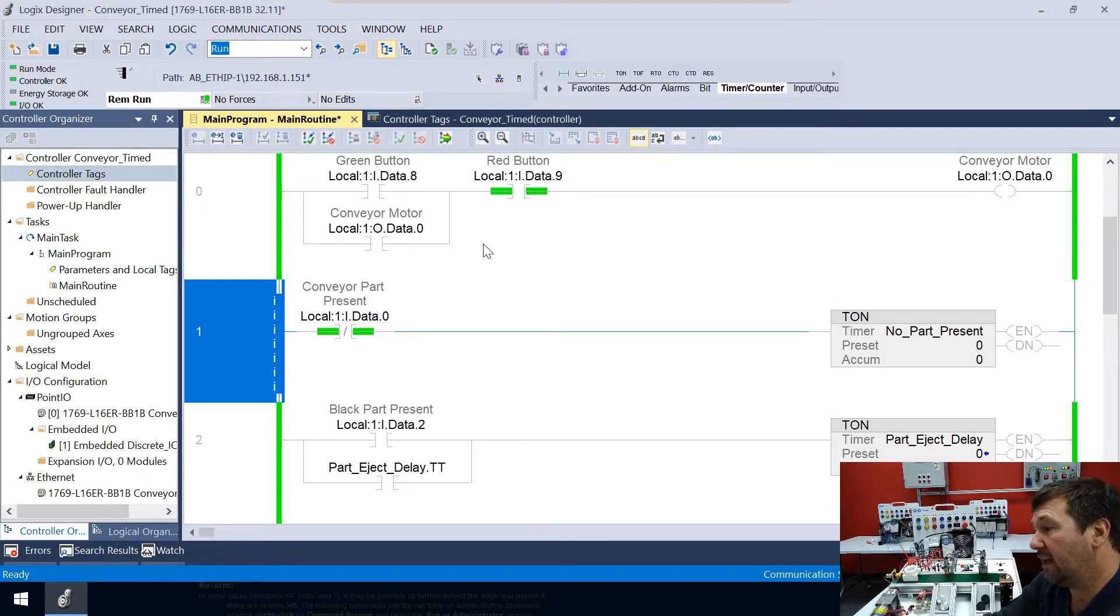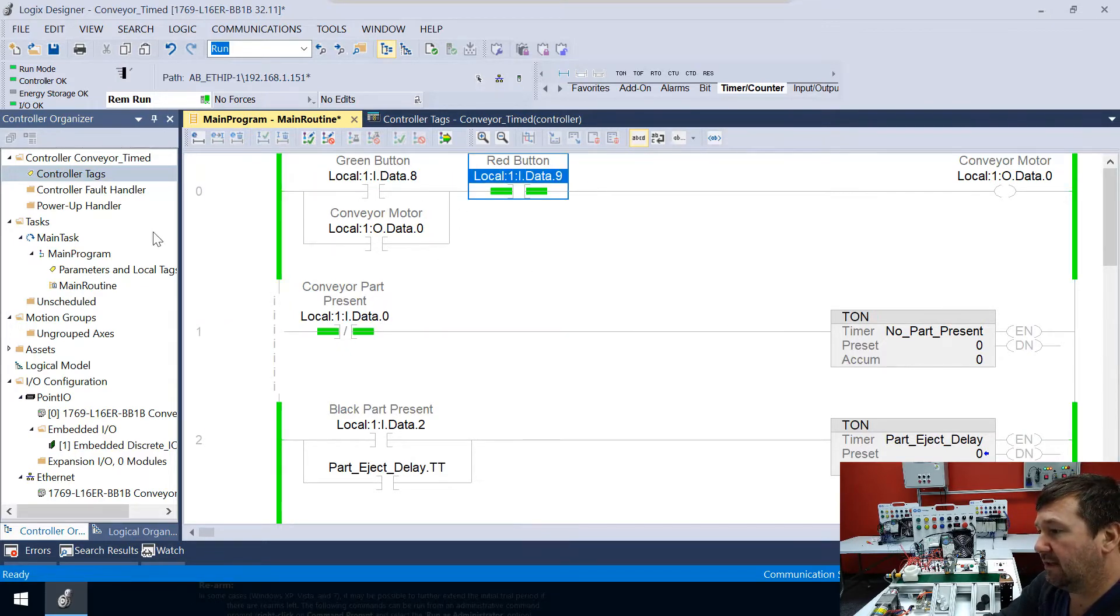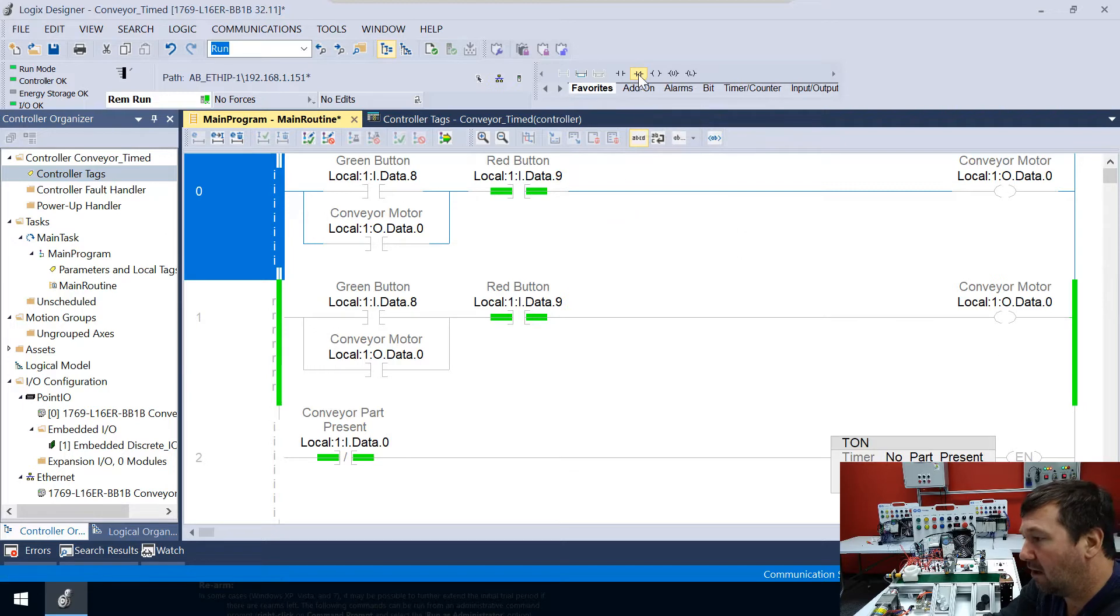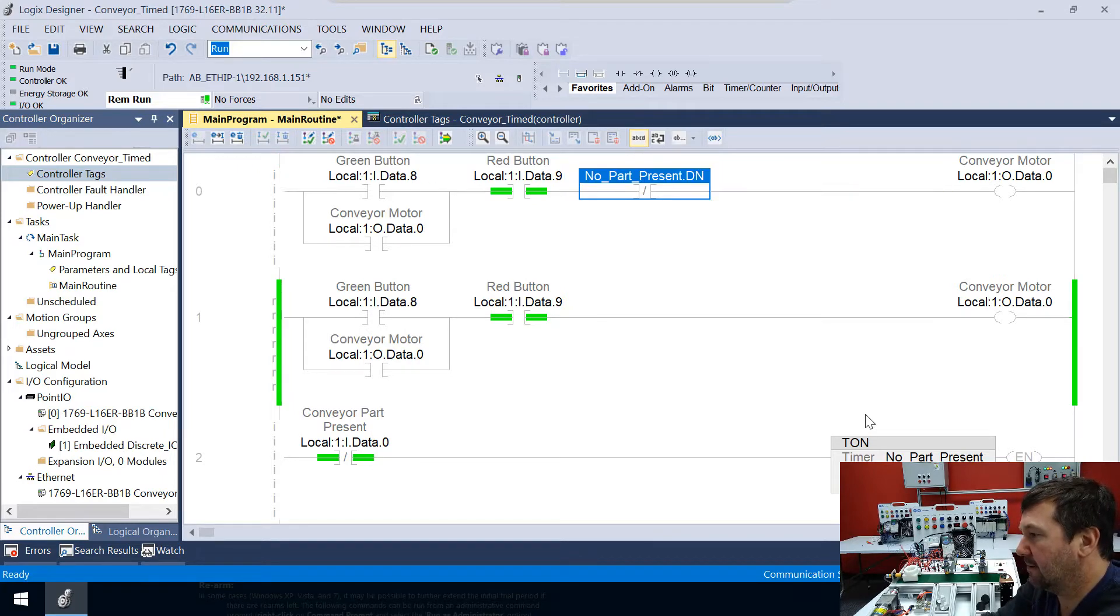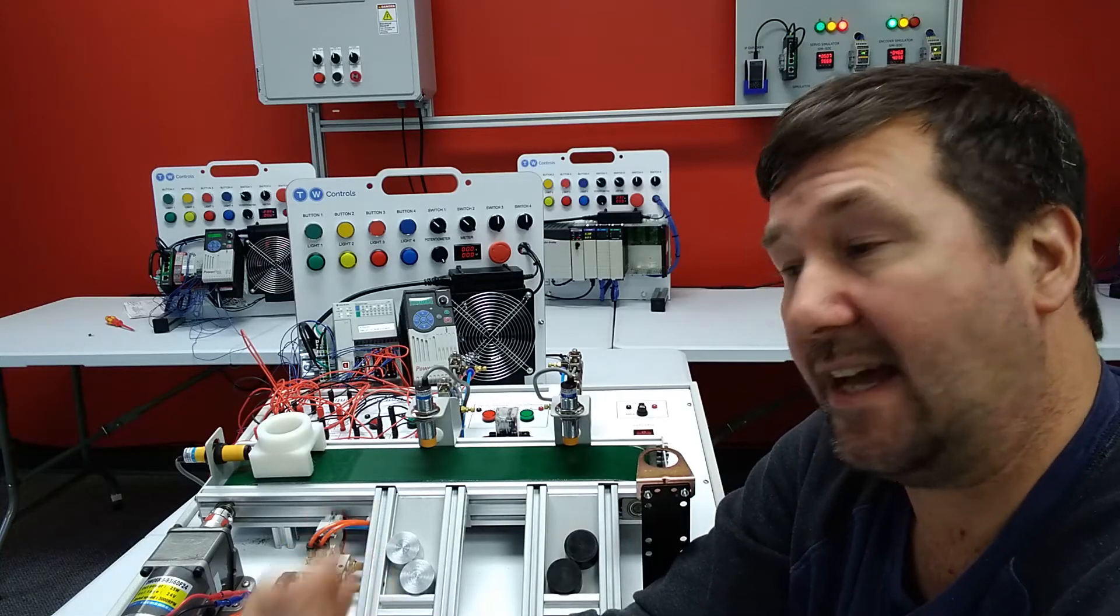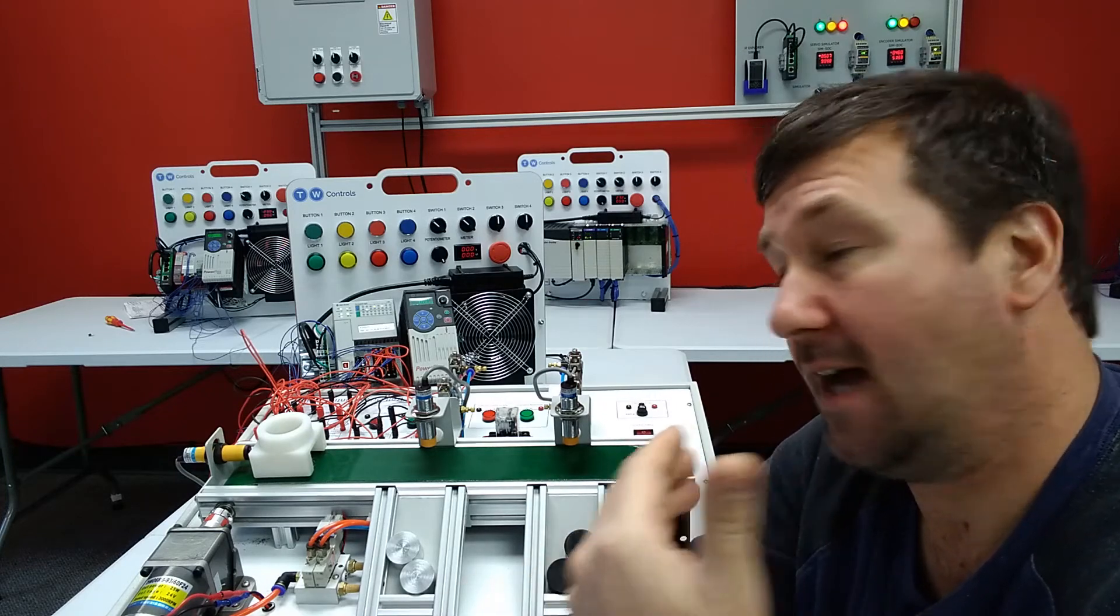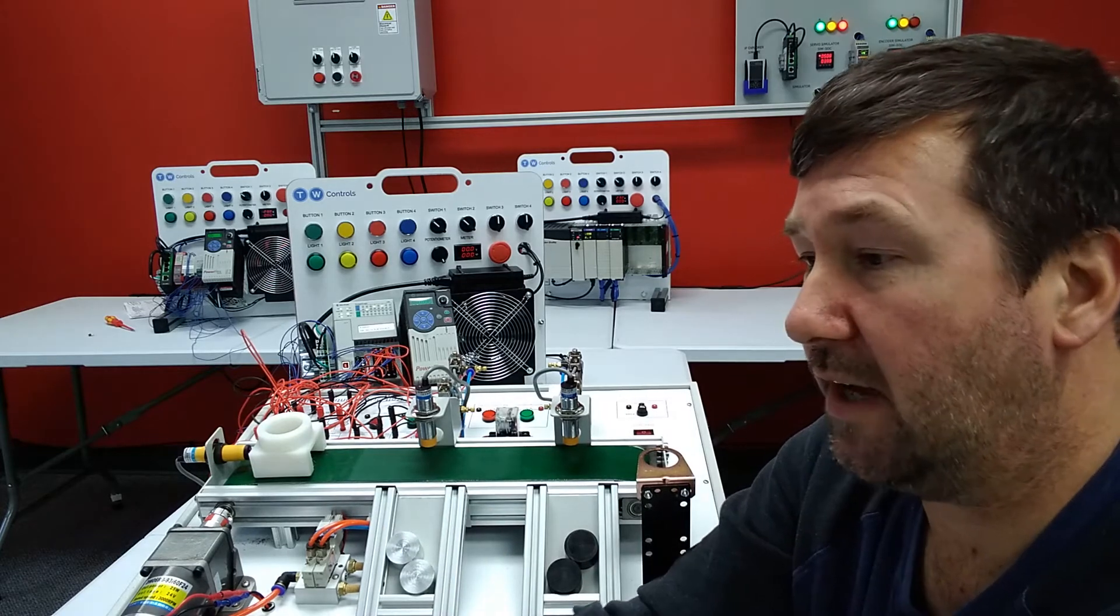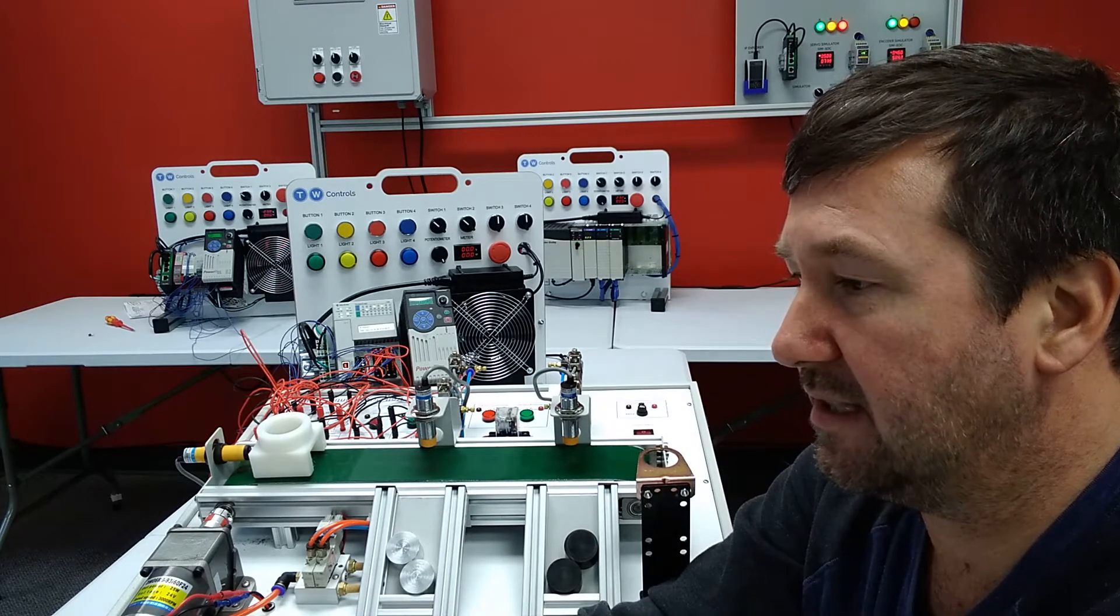So when this timer is done, we want to stop our conveyor. So all we're going to do is go up here and go to our favorites tab. And we're going to go for an examine if off. And we're going to look for No_Part_Present.DN. So what that means is as long as that timer has not timed out, or mainly we have not been 15 seconds without seeing a part, we're going to run our conveyor. Let's go ahead and put these two rungs into our PLC.